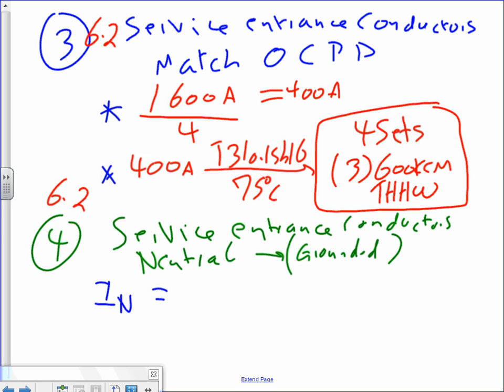So, gentlemen, what you're going to do, you're going to have 4 of these, 4 conduits like these. Imagine 4 conduits. Each conduit will have 3 conductors, 600 kcmil inside it. That's what we're doing. Now, somebody will ask me, what happened to the neutral, Chad? We need to go size the neutral, right? So we'll size our neutral. Any comments, guys, questions about that before we move? 4 sets, 3, 600 kcmil, THHW.